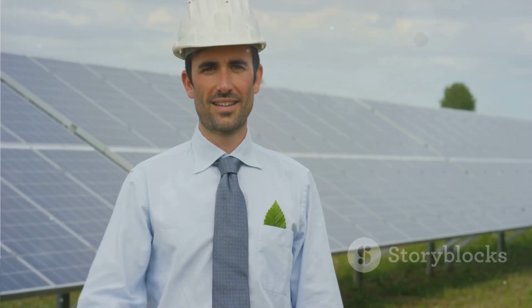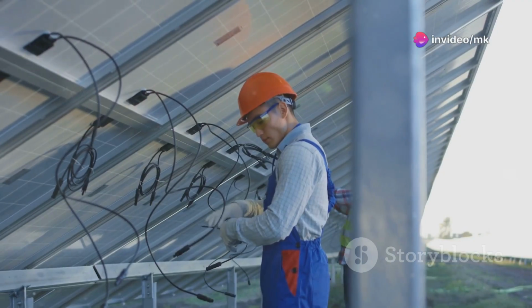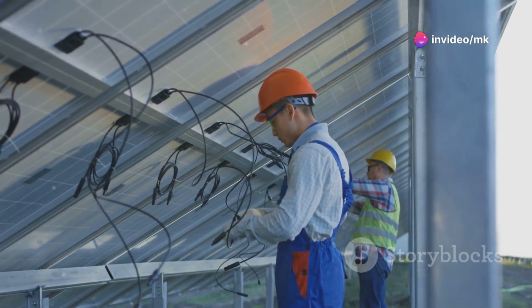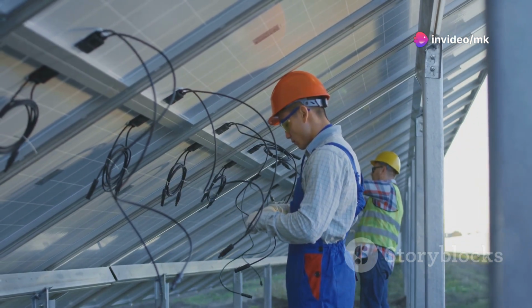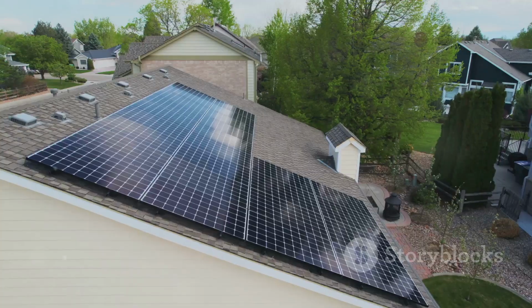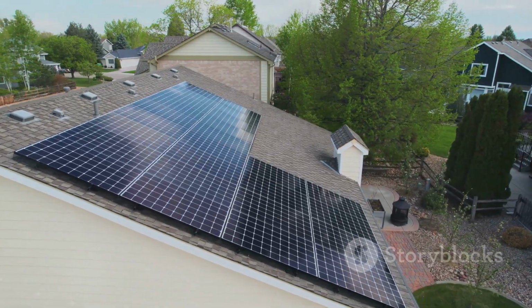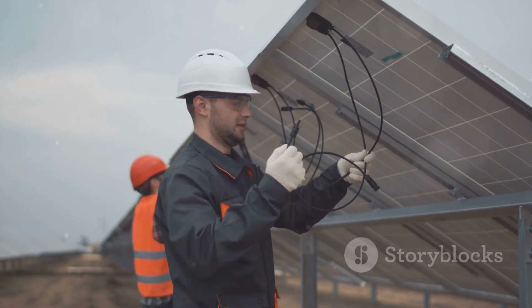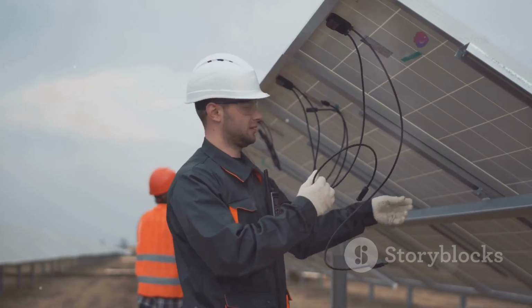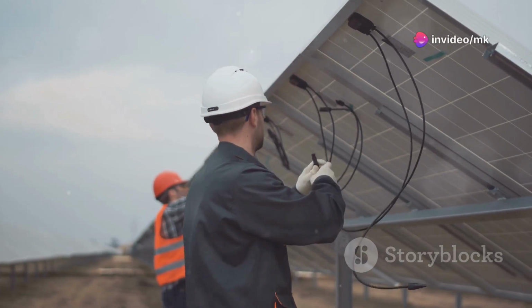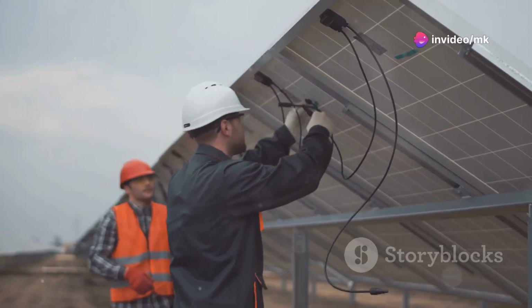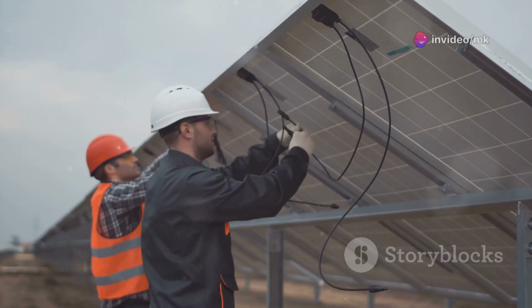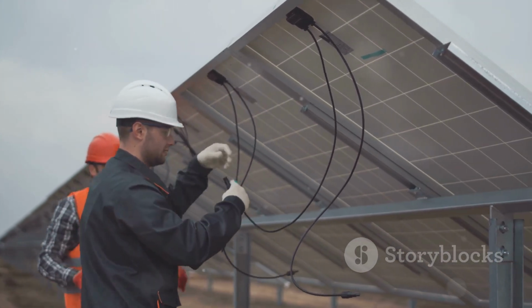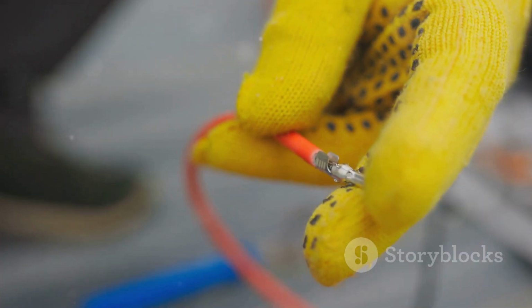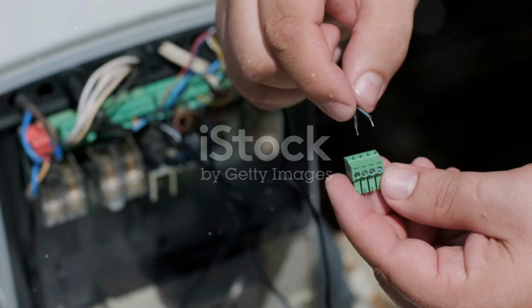Okay, components are sized and ready. Wiring is almost done. But there's one absolutely vital step left before even thinking about turning anything on: grounding, or earthing. This is your system's safety net, protecting you and your equipment. Here's where it all connects to Earth. First, solar panels and racking. Every single panel frame and the metal rails they sit on must be connected together with a bare copper or green wire, run down to your grounding system. This stops static and provides a safe path for faults.